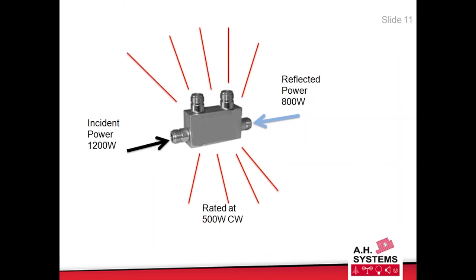Well, these guys were calibrating, so they didn't have the on-off situation going. They had CW as a continuous power going into the input there. And because they were struggling to achieve the field - you guys who have done low frequency immunity testing will recognize that you often struggle to get that field at the lower frequency - they had this amplifier turned right up, the best it could, giving out 1,200 watts.